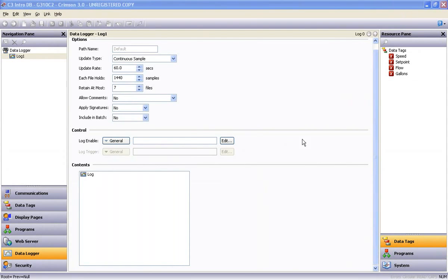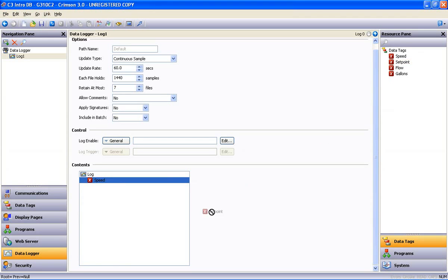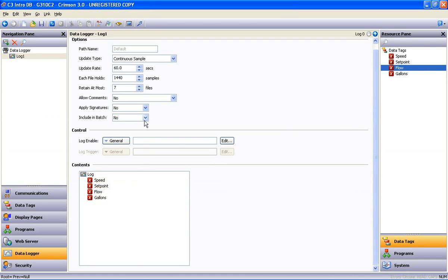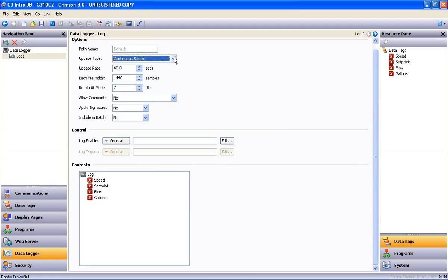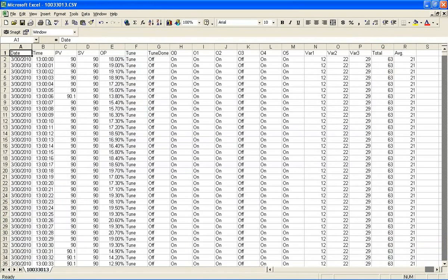What about data logging? After creating a log, simply drag the data to be logged into the contents window and you can multiple select items for this operation as well. And we will log the data at user programmable rates or on a triggered event. Then the information is stored in open CSV file format with automatic time and date stamp and can be accessed through applications like Microsoft Excel.